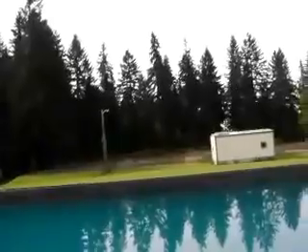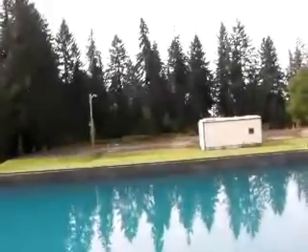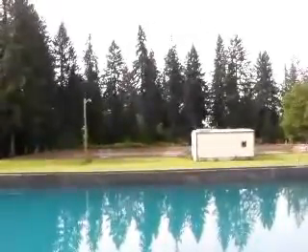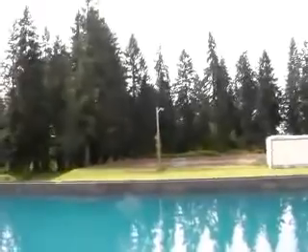Those are our lagoons, and that is where we go after we backwash. When we backwash our filters, the dirt, the material that we get from the backwash, goes out there, and then we let it settle out. Then we decant it, and when we decant back to the beginning of the process, because the state has required us to send it all the way to the very beginning again and start over. But it saves us a little extra money.